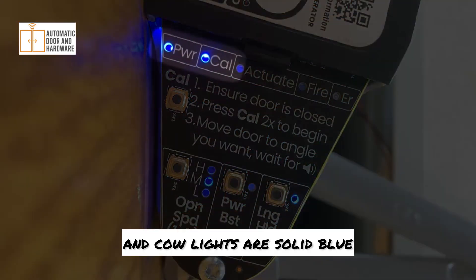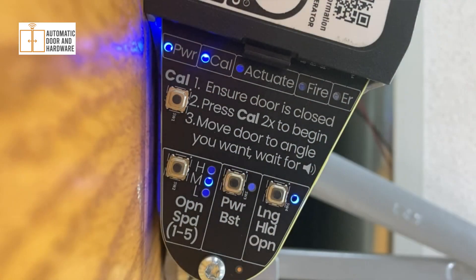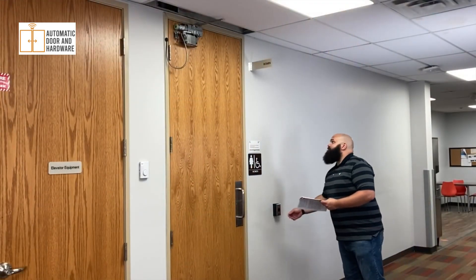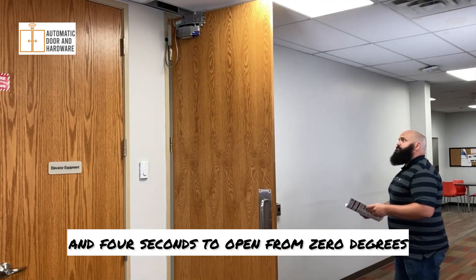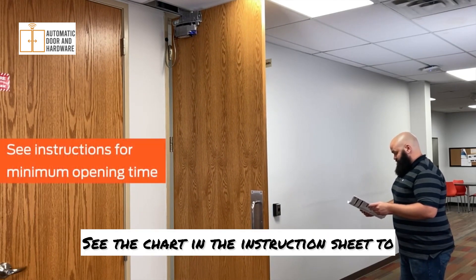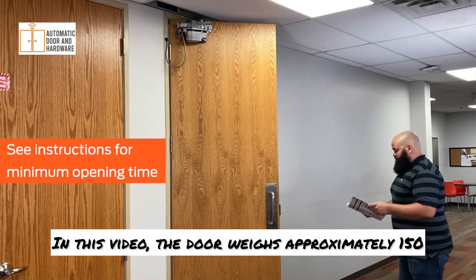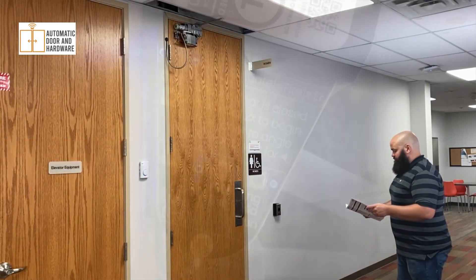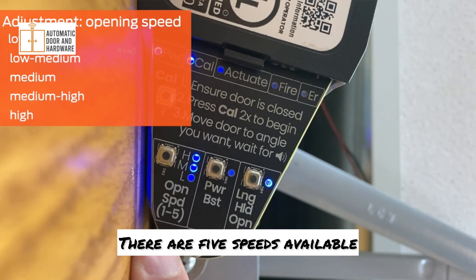Confirm the power and Cal lights are solid blue, and the actuate and fire lights are off. Turn the motor enable switch to the on position. Actuate the door and observe the opening. Depending on the door weight, it must take at minimum between 3 and 4 seconds to open from 0 degrees to about 80 degrees. See the chart in the instruction sheet to determine the minimum opening time for your door. In this video, the door weighs approximately 150 pounds, so the opening time is set to 3 and a half seconds. To change the opening speed, press the open speed button as shown. There are 5 speeds available.